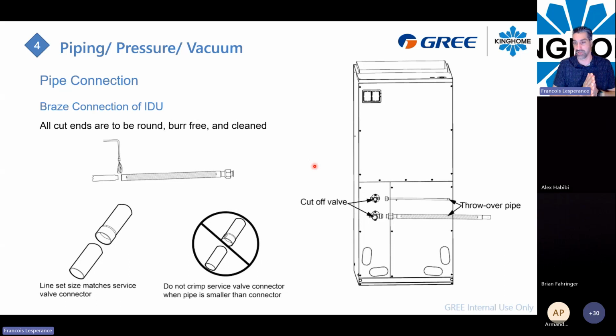When you get those units, you will have some kind of fitting already flared. This fitting comes with the unit, with the outdoor unit and the indoor unit, but it's not mandatory to use it. If you can just put in your piping and do your flare directly to the valve without using those extensions provided with the unit, that's great. If you avoid brazing, that's awesome. But the unit will come with this kind of connection.